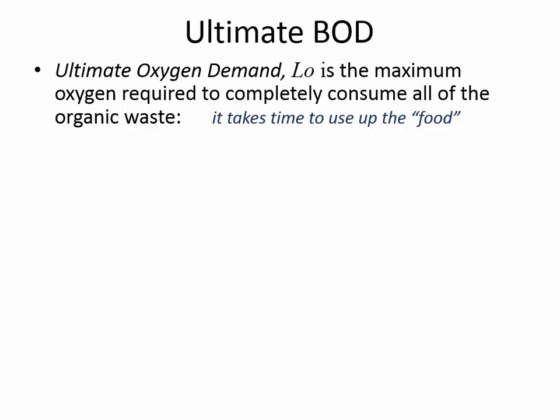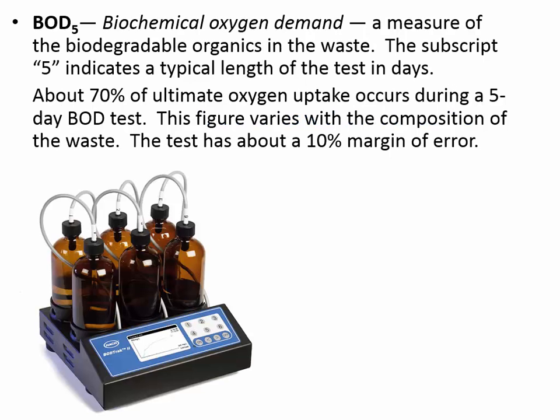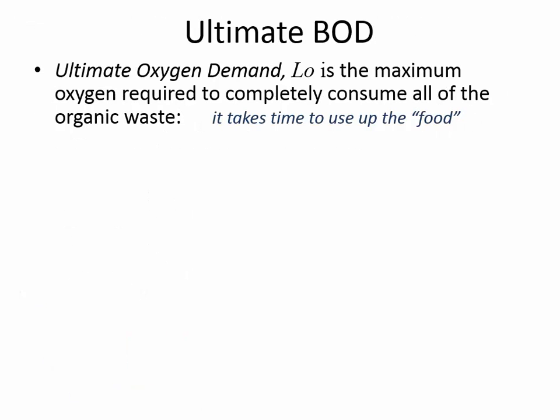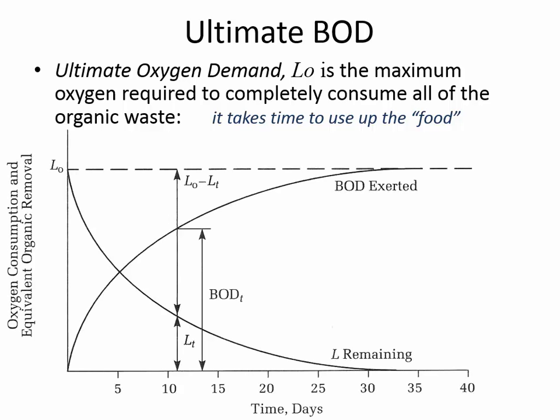When all of the BOD is used up, that's what we classify as the ultimate BOD demand. This first one, we were just talking about how much demand for oxygen is there during a 5-day period. But the bacteria are very resourceful. They'll break down every little molecule of energy that they can. And so it's not just the 5-day BOD that you have to be aware of, but the ultimate BOD, ultimate oxygen demand, L naught, is when all of the biochemical oxygen demand has been exerted, what is the amount of oxygen required to do that.